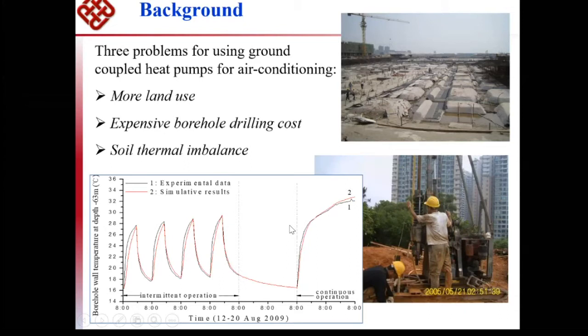After several years of operation of most systems, all the systems, we found that the COP is much lower than expected, than the design value. Then they have to install additional cooling coil systems, cooling tower systems to add more cooling capacity for summer and winter heating capacity. So there are three main problems.